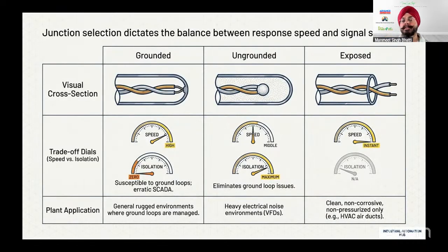The third, as it shows, is called the exposed one. It means the sensor is exposed directly to the media. Here you will see the response is very fast, but we do not have any kind of isolation here. So there is no isolation here. So it's susceptible to any kind of pressure changes, high level of temperature changes, wind changes and all that stuff. So it has to be used on a very, very clean application.